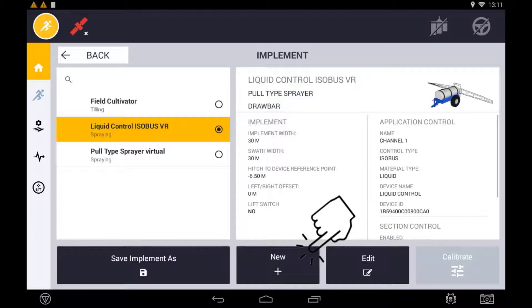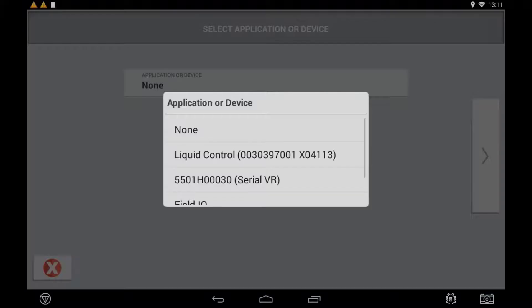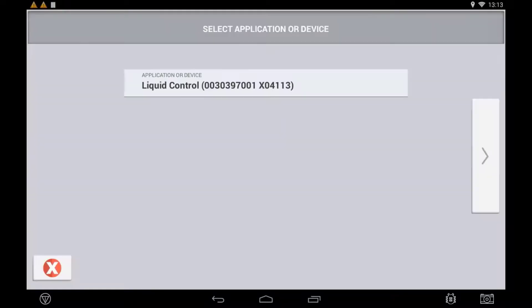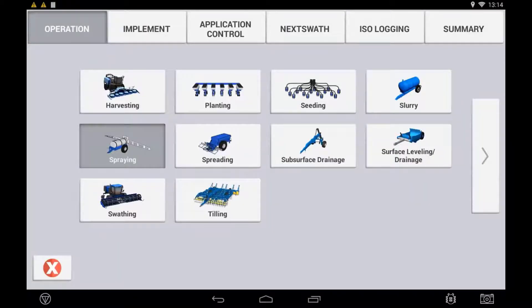When selecting the application device, if your ISOBUS ECU is Task Controller compliant you will see it listed in the available devices. If more than one ECU needs to be configured for your implement, select the ECU that you want to be displayed as the primary channel. Press the next arrow and continue the configuration. Once the ECU connects, basic information such as the implement type and widths will pre-populate some of your implement settings.